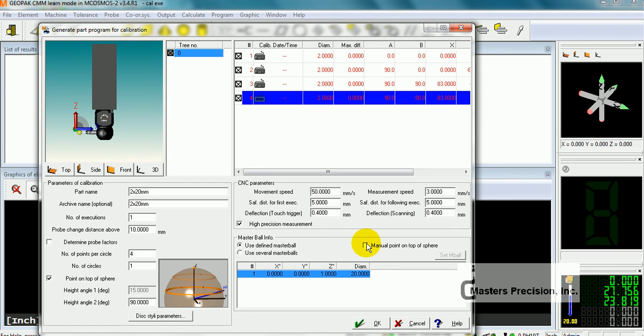If you select manual point on top of sphere, this is going to require you, when you run this program, to physically touch the first point on top of the sphere every time. However, if your master ball has been measured in the same spot every time on the table, you can use a defined master ball position. Make sure high precision measurement is checked. Your movement speed is how fast the machine is going to move across the table. Your measurement speed is how fast it's going to move when it takes the measurement itself on the sphere.